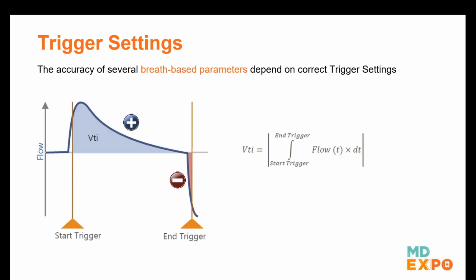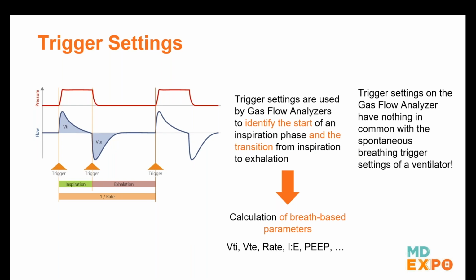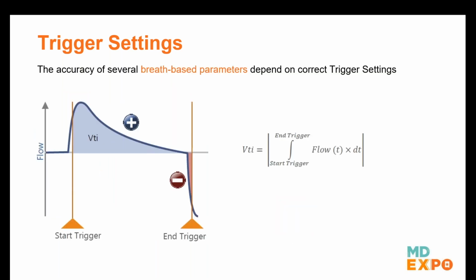All right, another thing we need to make sure of, and I think that makes sense, is that our trigger settings are as close as possible to the real breath cycles of the ongoing ventilation. This is going to be one of the challenges we're going to talk about, because if we are not close to reality, then our calculated values will be wrong. Here we have an example of inspiratory tidal volume. This is an inspiration phase, so this is the flow over time, and mathematically what the ventilator tester, the analyzer, is going to do is integrate the flow over time from the start trigger to the stop trigger, and then say, okay, this is the shaded part under the curve. Mathematically, this is going to be my inspiratory tidal volume.